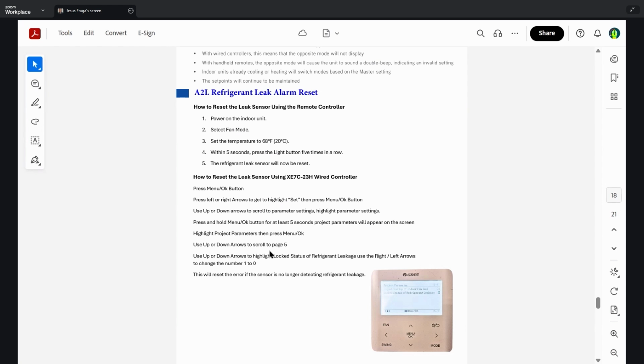Use up and down arrows to scroll to page 5. Use up and down to highlight lock status of refrigerant leak sensor. Use the right/left arrows to change the number from 1 to 0. This will reset the sensor and it is no longer detecting a refrigerant leakage. So that's how to reset. Pretty much you have to go through the parameter settings and actually physically change the lock status of the refrigerant leakage. What that means is you have to go in and change 1 to 0 to be able to do the reset of the refrigerant leak sensor.